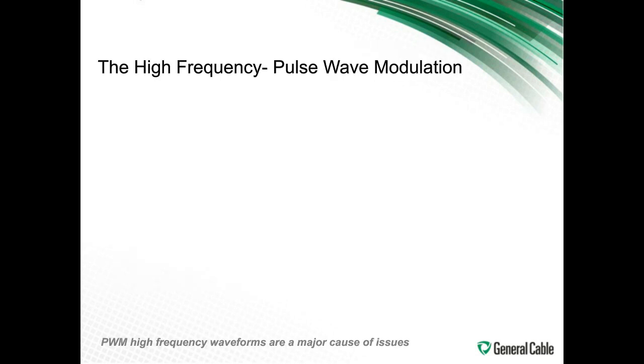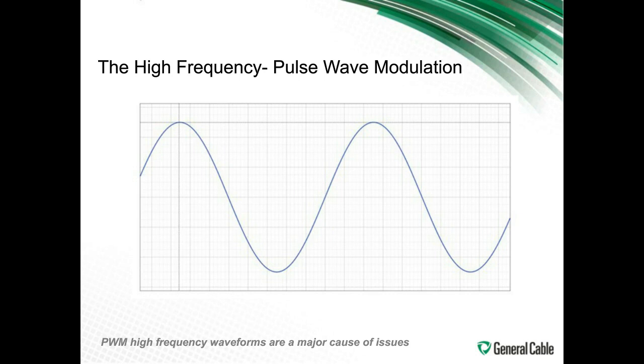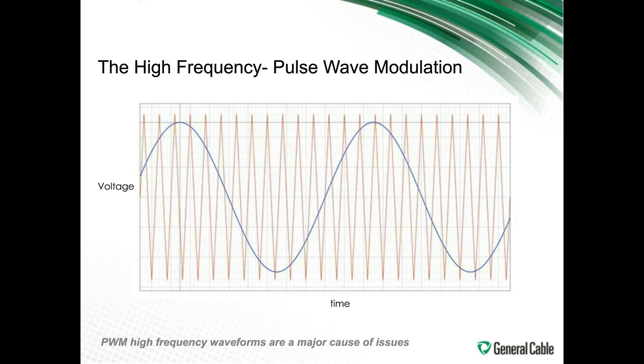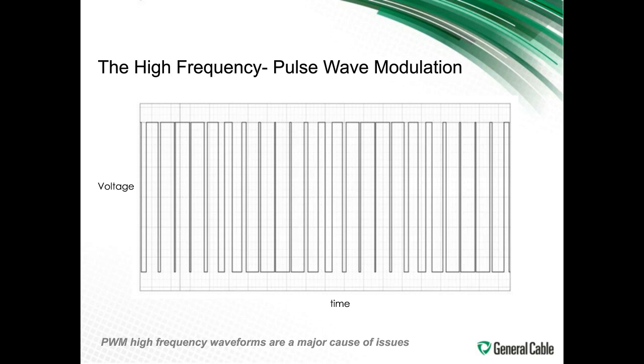What is high frequency pulse wave modulation? In a normal system, you have a 60 hertz waveform, which is a sinusoidal waveform. With the pulse wave modulation that the IGBT semiconductors or the actual drive creates, it takes pulses of voltage and digitizes them, creating amplitude pulses in a sequence that makes a pseudo waveform. Even though it's a square type of form, it creates a voltage waveform that becomes kind of like an AC waveform. But in doing so, it is a digitized process, and this causes the problems. Herein is the evil.